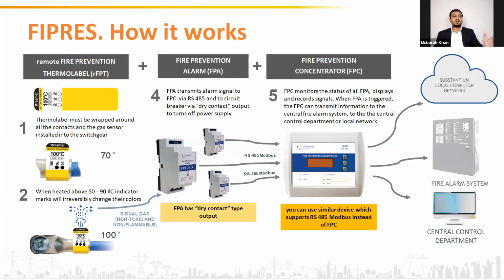Okay, so this is the overall system configuration. I'll do one small revision. Remote fire prevention thermolabels, RFPTs, will be installed on each joint. When the temperature of the joint reaches 50 degrees Celsius, the 50 degree pre-indication dot will change its color from white to black. Similarly, 70 and 90 will also change at the respective temperatures.